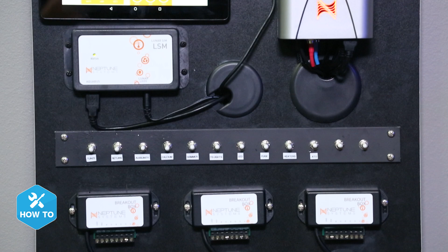Tools we need for today's install are going to be a precision calibration thermometer like this one from Traceable, or 2 or 3 more inexpensive thermometers that we can use to average the tank temp. Out of the box, the first thing I like to do is set the red calibration ring to about halfway between its highest and lowest setting.